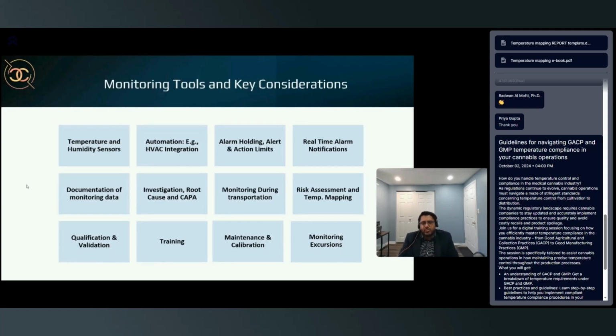Temperature and humidity monitoring units in the HVAC have to be properly validated and compared against your own calibrated sensors. With HVAC sensors, you don't know how they're placed, whether they're inbuilt, touching the wall, or not even at ground level. All of that can lead to different values compared to your calibrated sensor. So don't rely blindly on your HVAC integrated sensors.